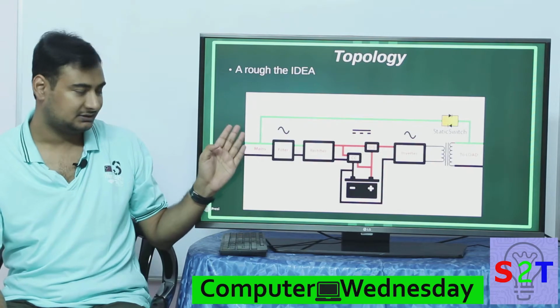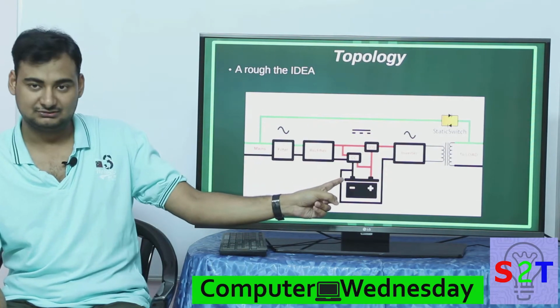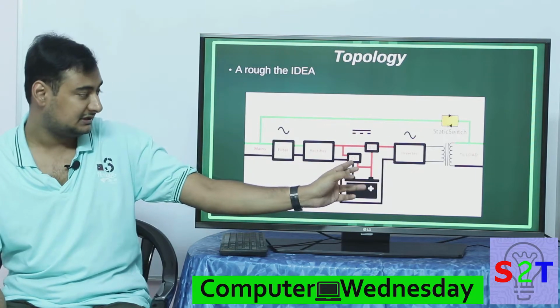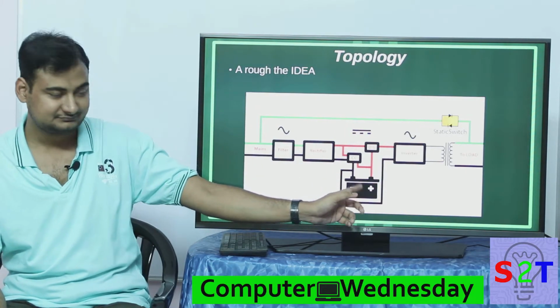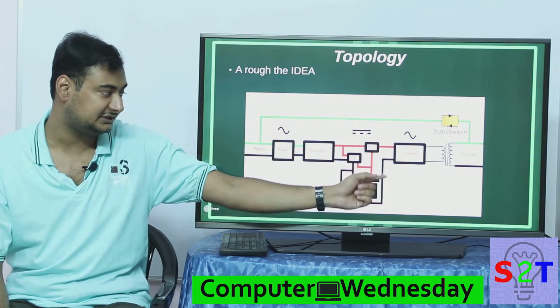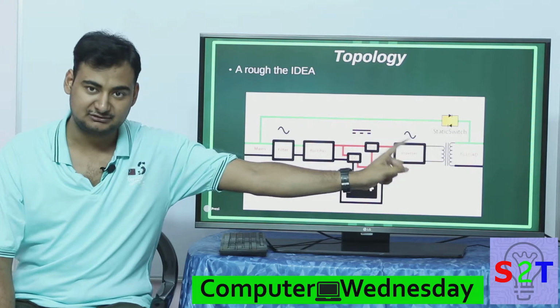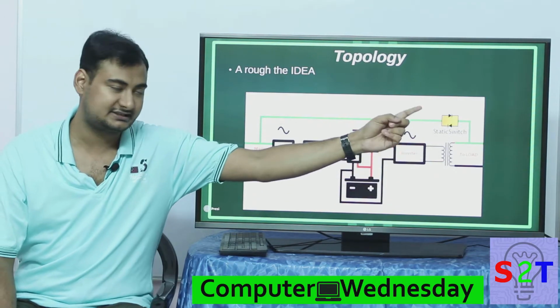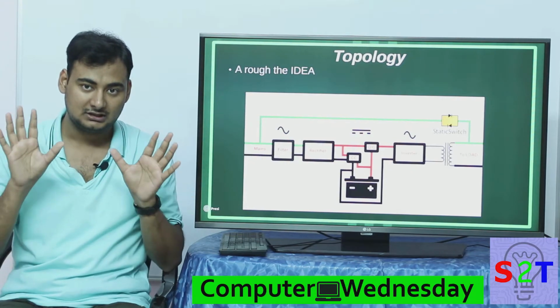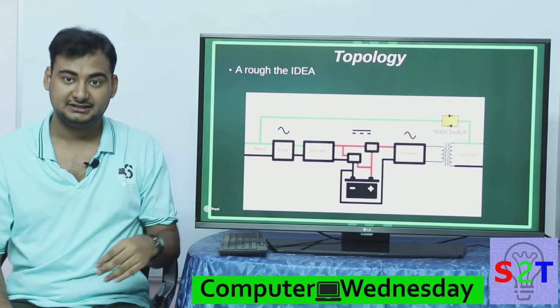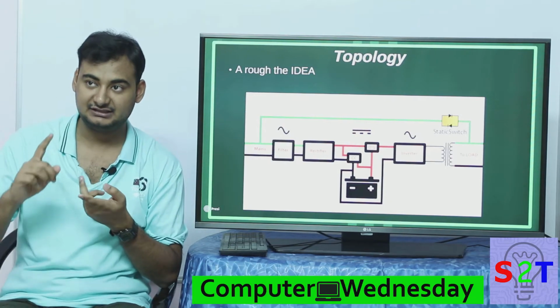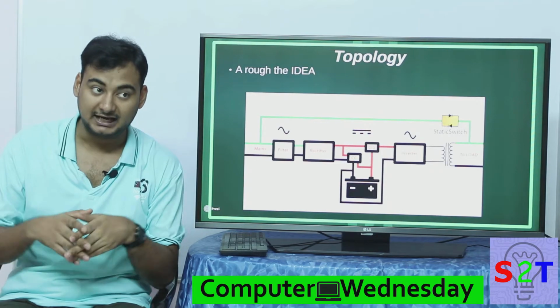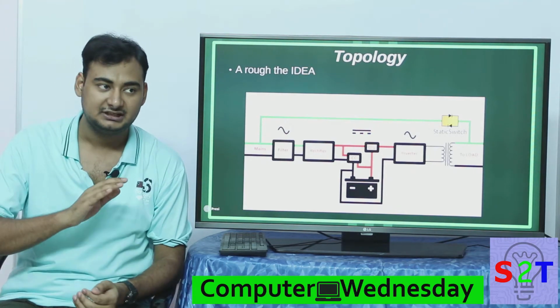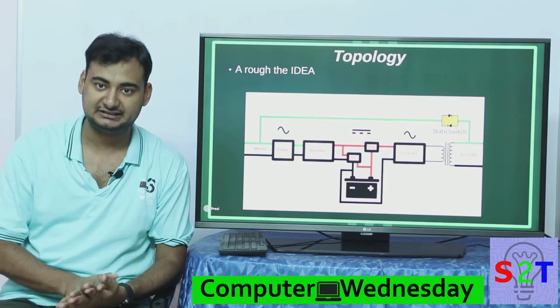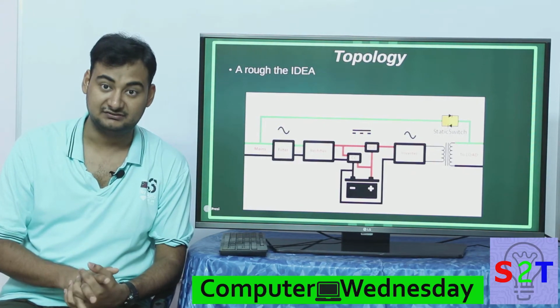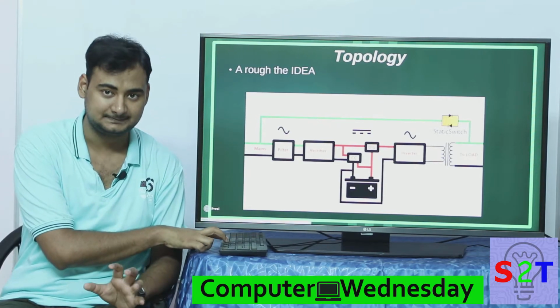So a quick summary: you have filtered, you made AC into DC, you feed that DC into the inverter plus the charge controller, and it goes through a diode gate. When the power goes off, the diode gate directly bridges the battery to the inverter, and from the inverter you get to a transformer which galvanically isolates your whole thing, and you get a stable load output. So this is the whole idea of double conversion. Because you are always running on DC and the inverter is the one controlling your frequency and voltage, there is no fluctuation. Ideally, of course there will be minor fluctuation here and there, but ideally it's so low that all components can last very long. So this is the whole topology.